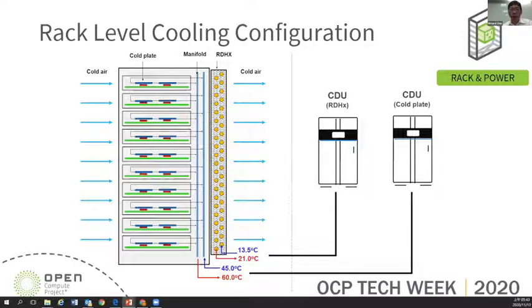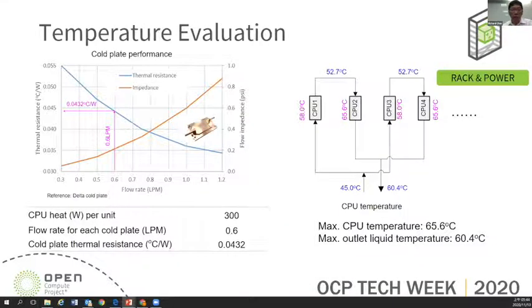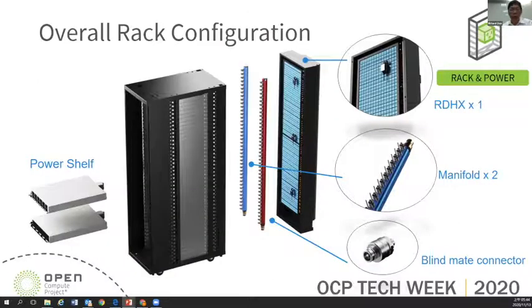There are 2 coolant loops for the rack. One is 45 degrees C for CPU cooling. The other is around 14 degrees C to the rear door heat exchanger, to cool down the air temperature from the rack. In a traditional air-cooled heat sink, it is very difficult to have lower than 0.1 degrees C per watt thermal resistance. However, for cold plate cooling, 0.05 degrees C per watt is a typical performance. This can easily solve over 300 watt CPU heat. The cooling system in the rack is with a pair of manifolds and a liquid to air heat exchanger in the rear door.